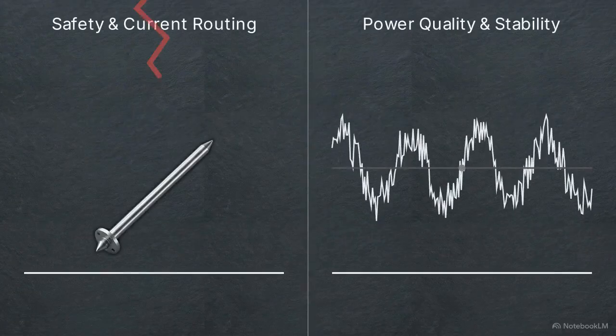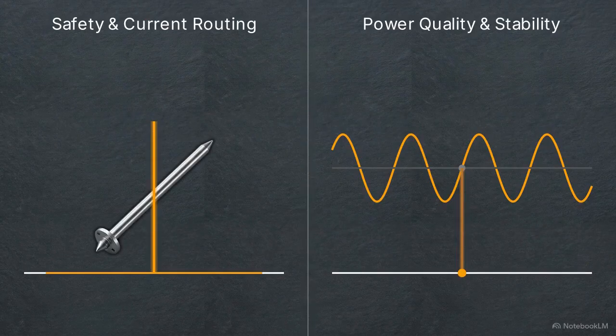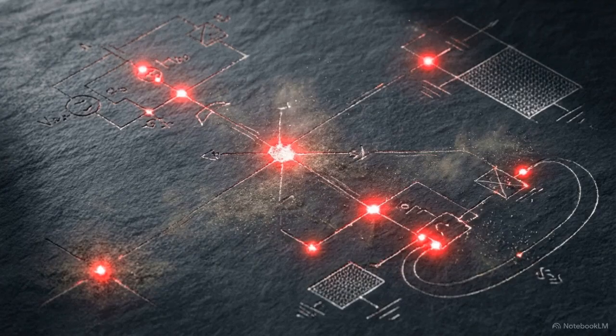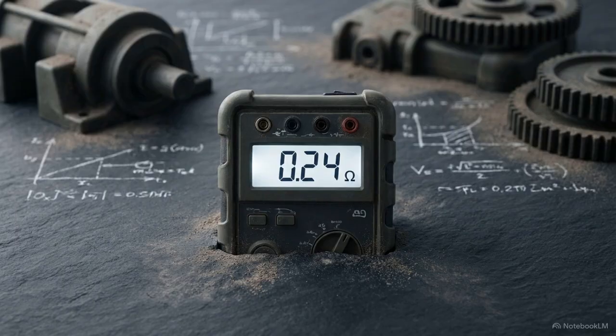Meeting these precise resistance thresholds ensures the safe routing of rogue currents and guarantees the baseline power quality of the network. Without a verified low-resistance connection to the Earth, the isolation of circuits fails and the stability of the entire power grid degrades. Validating this grounding pathway through rigorous field testing remains a critical discipline in the application of fundamental electricity.